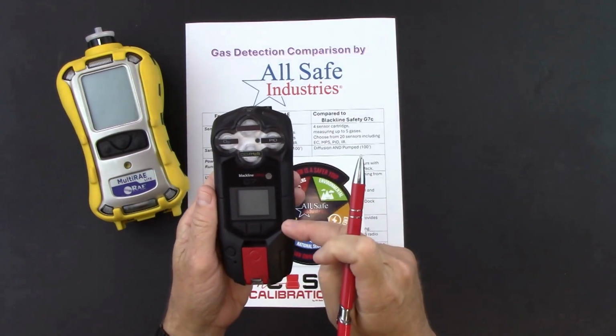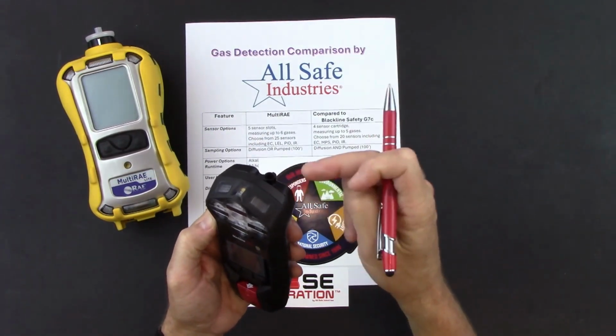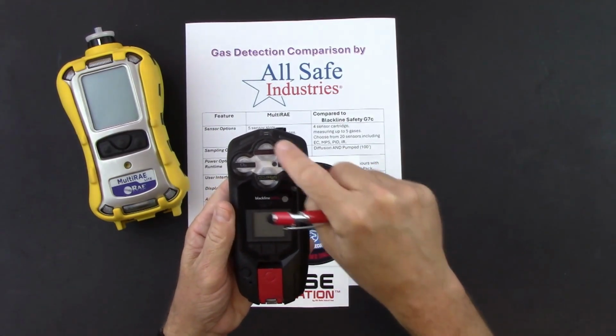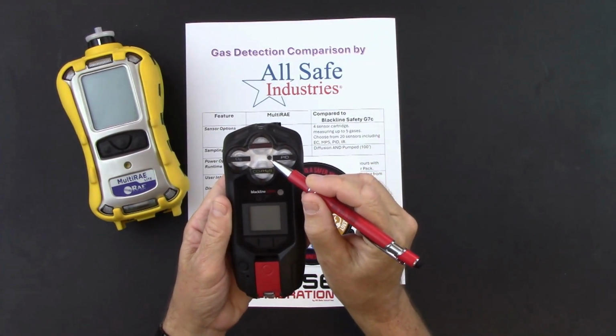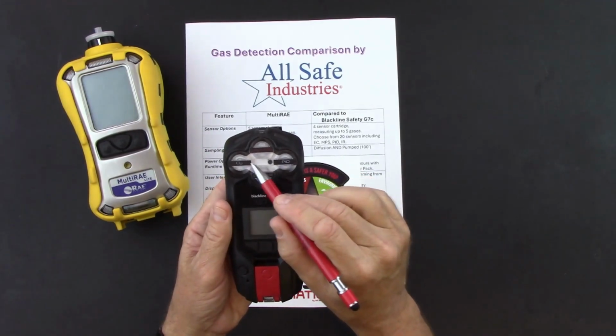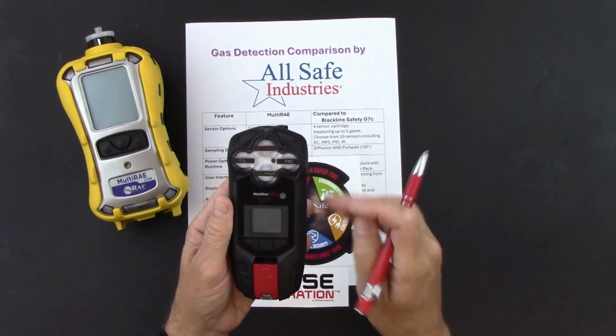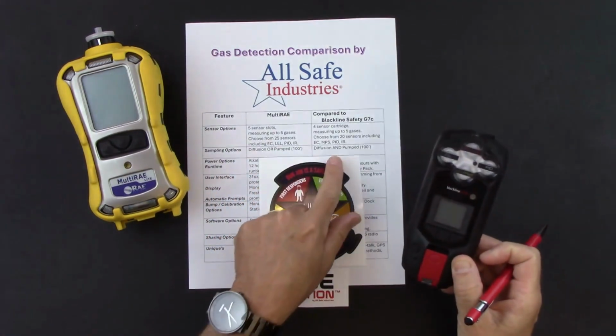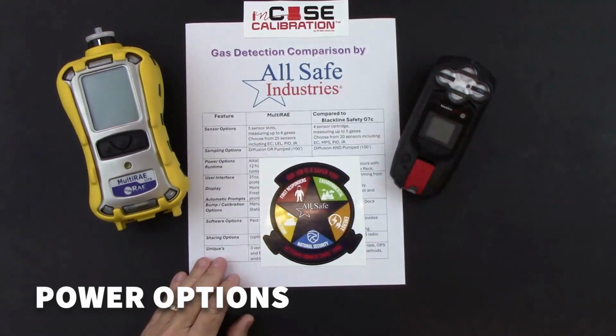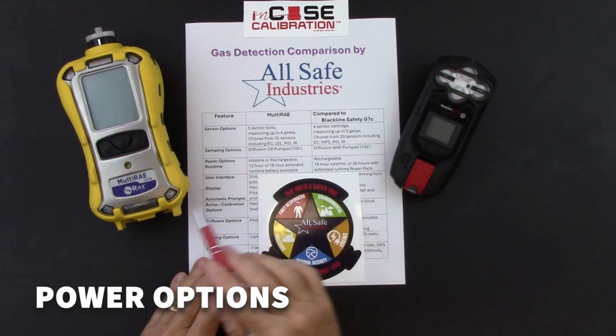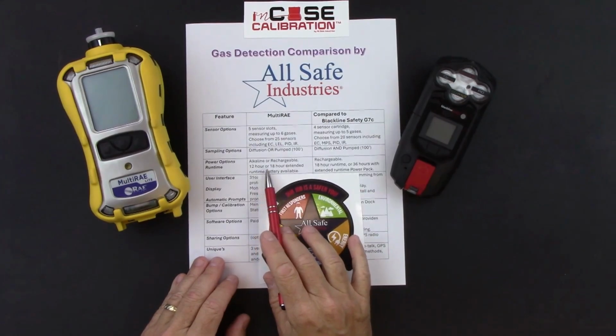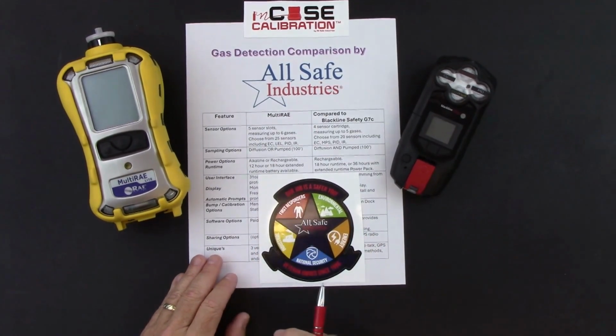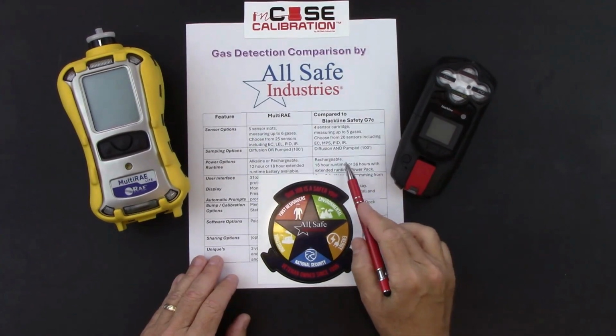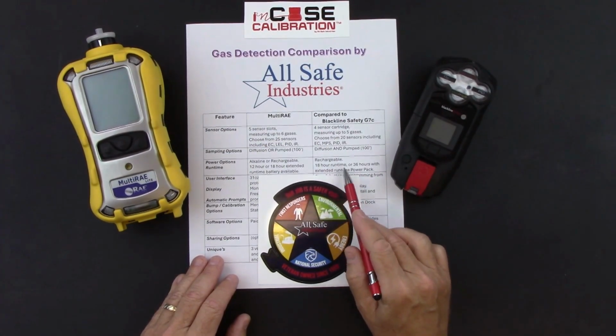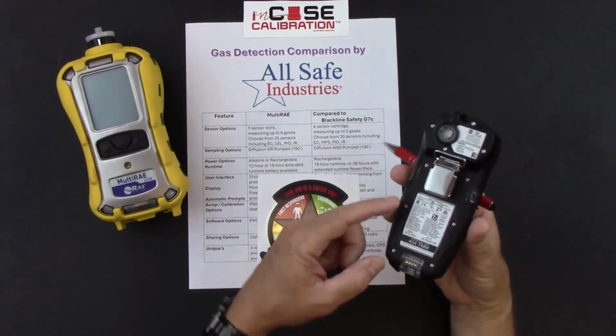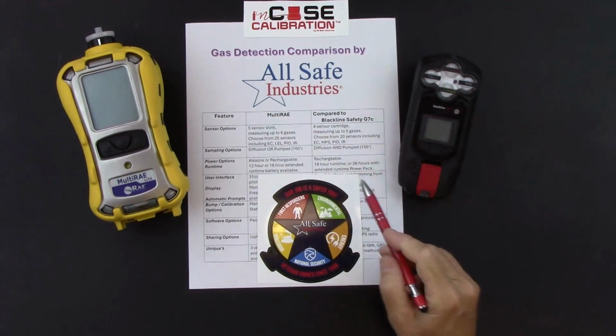So when I go through the menus to activate the pump, once the pump is running and I've tested it, now I can use my pump to draw gas samples to the sensors, and the gas sample comes up through that port right there, and then it's distributed to all 4 sensor slots in the cartridge. So the G7c is diffusion and pumped. For power options, we've got alkaline or rechargeable for the MultiRAE. You'll have 12 hours of runtime or 18 hours using their extended runtime battery pack that's available. For the G7c, it is a rechargeable instrument, and the battery on here runs 18 hours, but you can also connect a power pack to the back of the unit that would double your runtime to 36 hours.